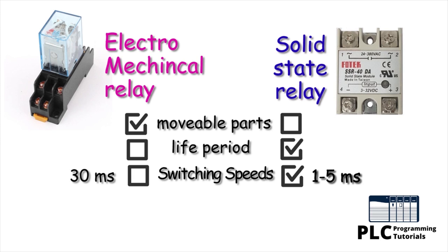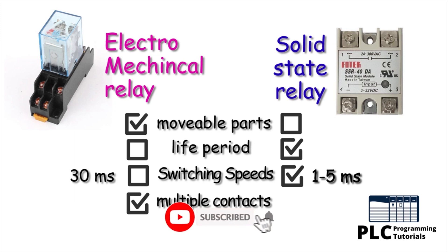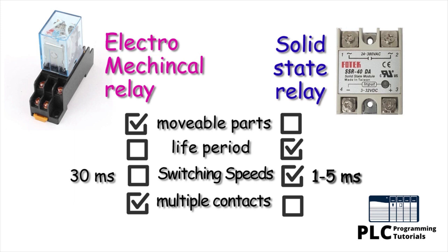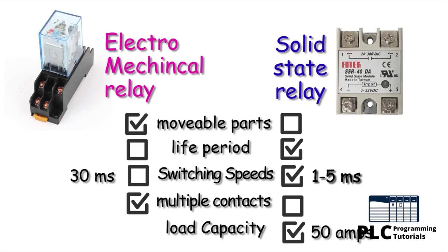The electromagnetic relay normally comes with multiple numbers of potential-free contacts. This makes the electromagnetic relay more flexible and adaptable in machine operation, meaning we have plenty of spare contacts to turn on or off multiple field devices operating at different voltage levels with a single relay. Regarding current-carrying or load capacity, nowadays SSR is more preferable — it can go up to 50 amperes, while an electromagnetic relay with movable contacts can only go up to 10 amperes.